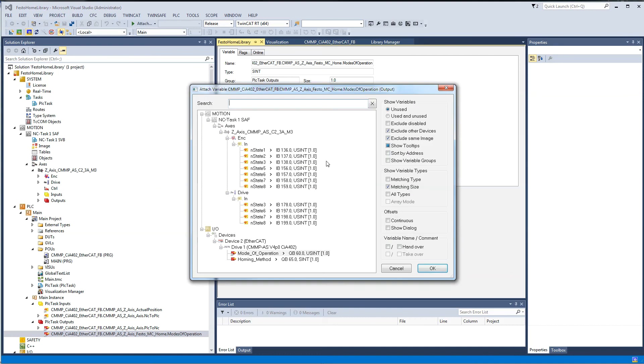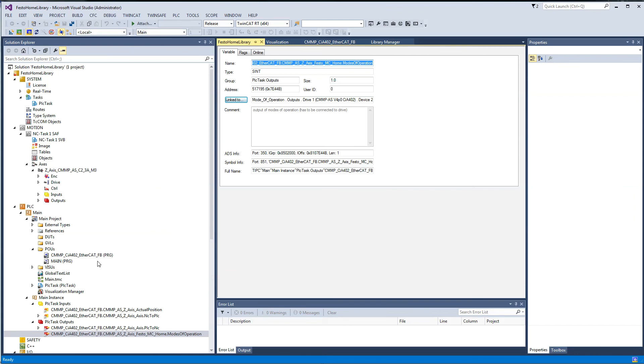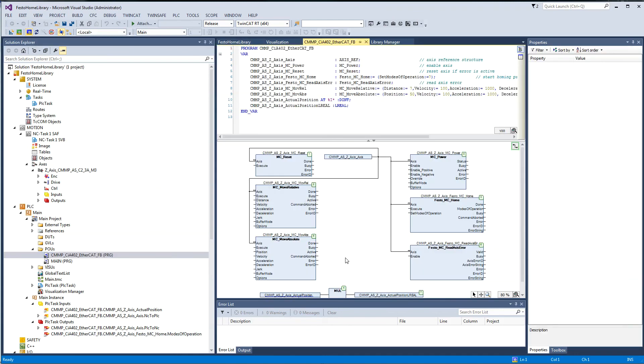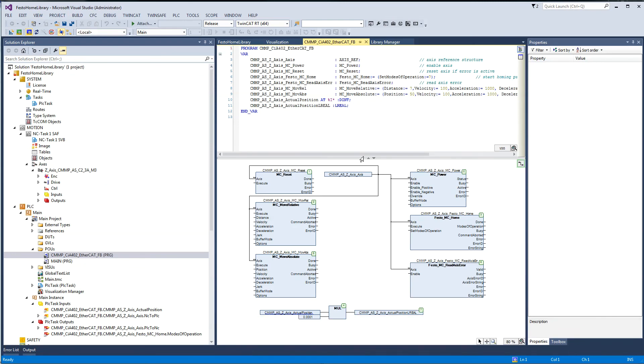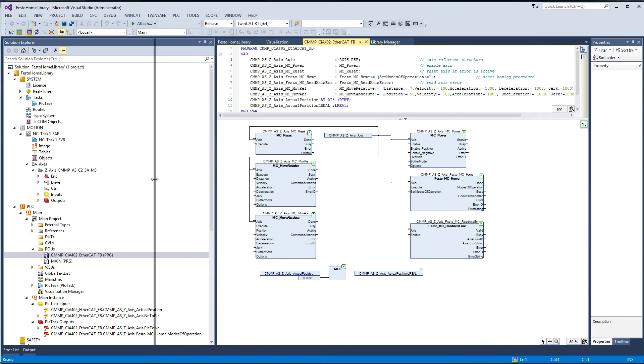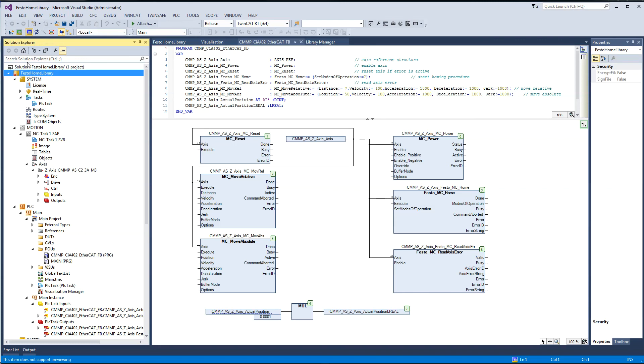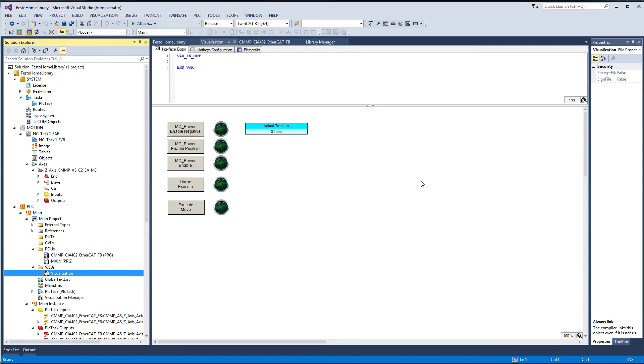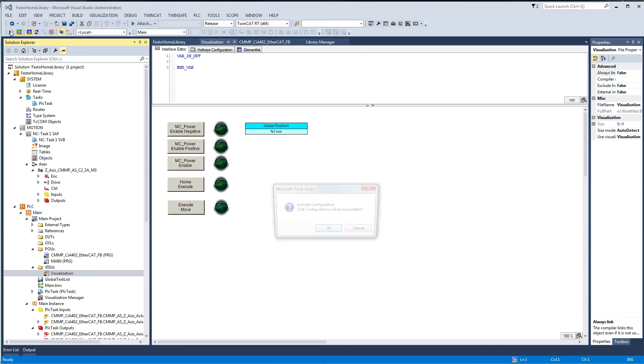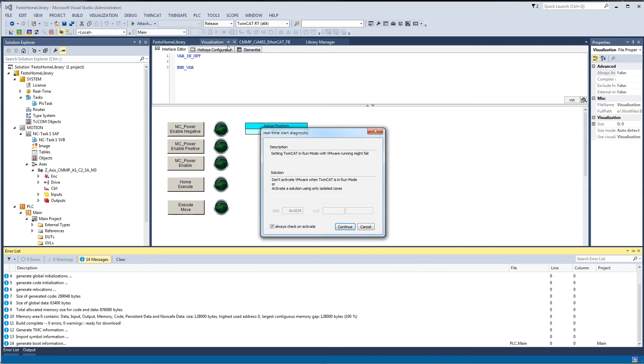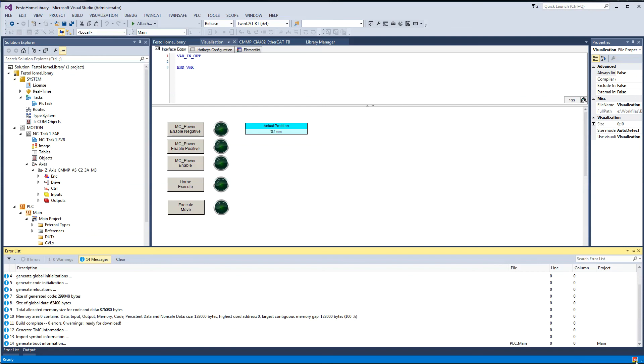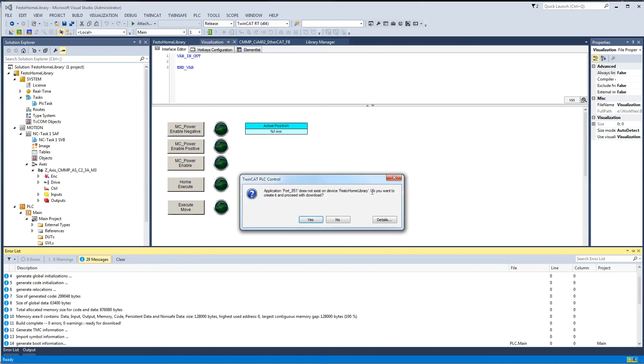The last thing to do here is the link, which I've done already. I did my code in CFC instead of structured text just for better visualization here. We'll go online in a second here. I'm just converting some stuff here. I'm going to run it and I also did a visualization. I'm going to activate the configuration, put it in run mode.